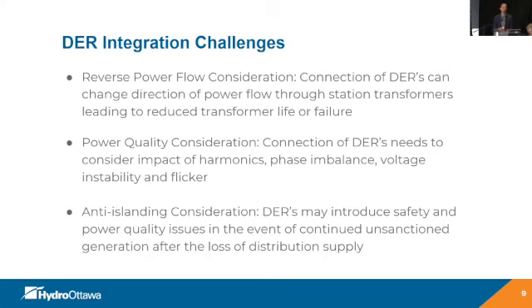There are many power quality considerations as an engineer that we have to consider, from harmonics, phase imbalance, voltage instability, and flicker. And again, as we have more DERs connect, especially in clusters, that's compounded. And then lastly, we have anti-islanding consideration, which does have power quality issues, but even more so safety. We want to ensure that when a DER is connected, especially in higher concentration, that they are not operating unsanctioned if there's a loss of the utility supply for safety reasons.